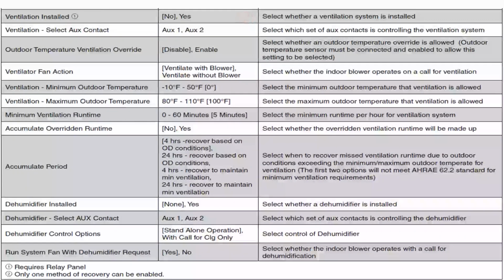If we have a fresh air damper, we're going to choose yes. And if we have it wired into the TAM9 auxiliary contacts to close the contact, you could change it from normally open or normally closed. Do we want that fresh air damper to open up and then the indoor fan to run? Outdoor temperature ventilation override, so we can select an outdoor temperature override. Ventilator fan action: ventilate with blower, ventilate without blower. Most of the time it's with blower because we want to bring in fresh air.